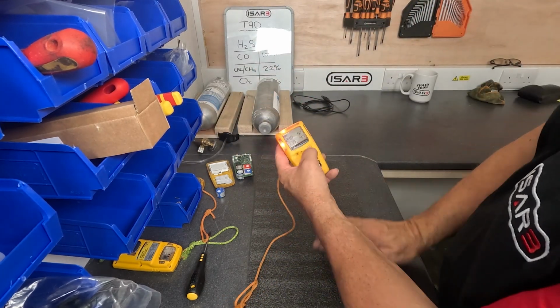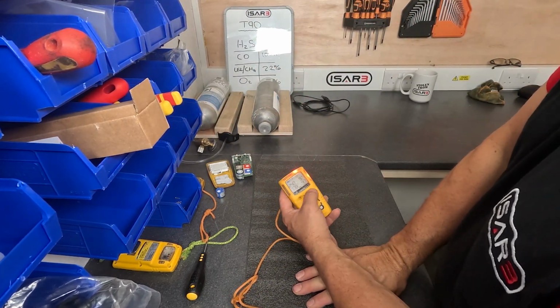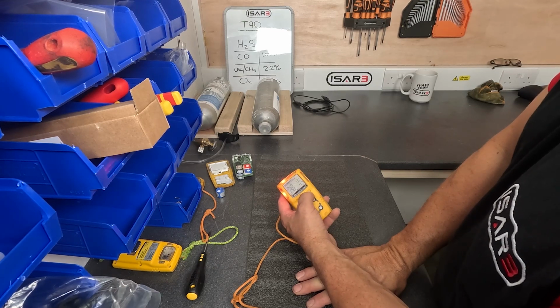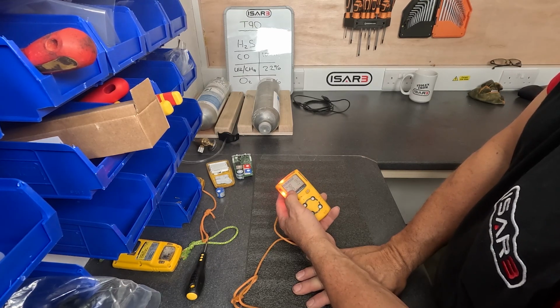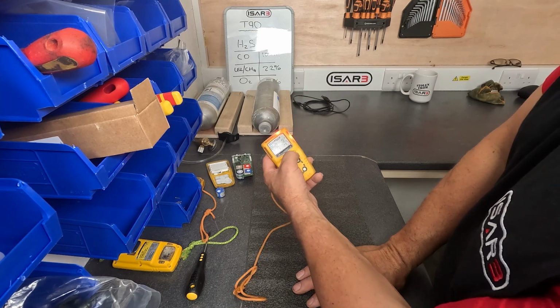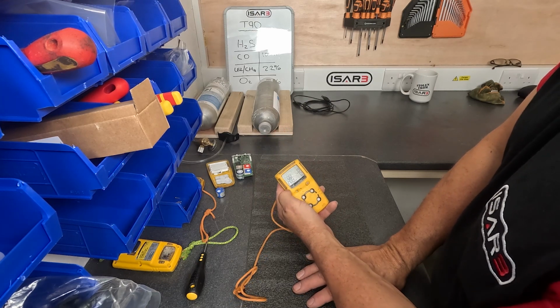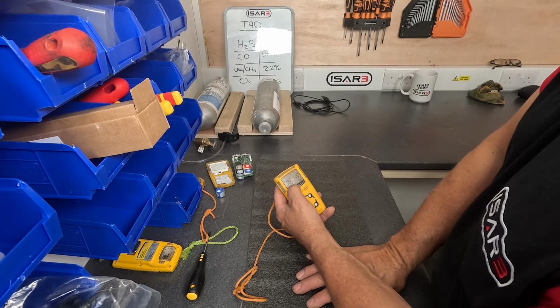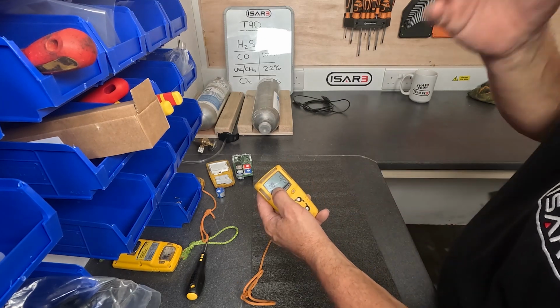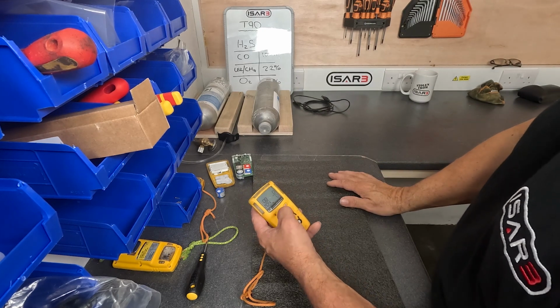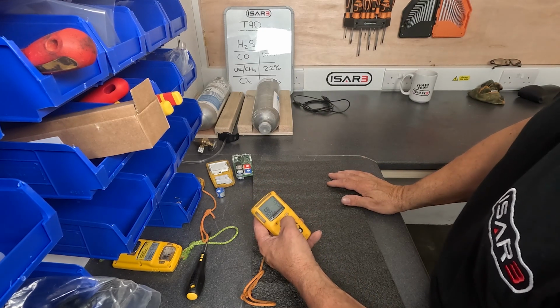So we set our gas detectors to latch, so as soon as I cancel the latch on here, the numbers should go back to normal with a possible lag on the oxygen. It takes a little bit longer to reset. So there you go, everything's gone back. The oxygen's sitting on 20.4. Sometimes these will reset, and sometimes when you clear them, they'll bump back to 20.9.